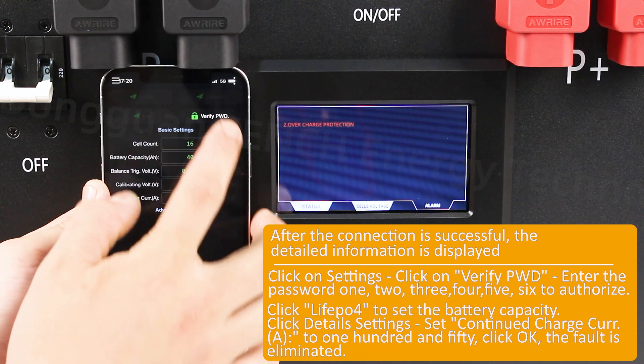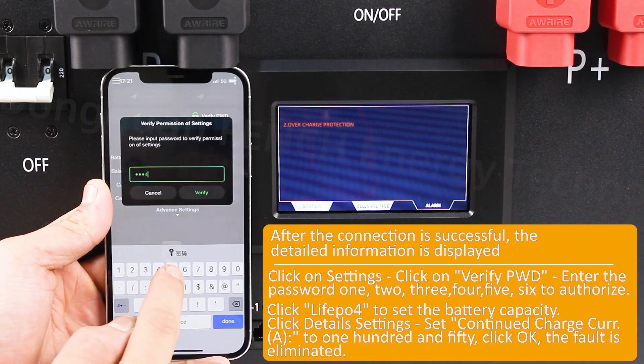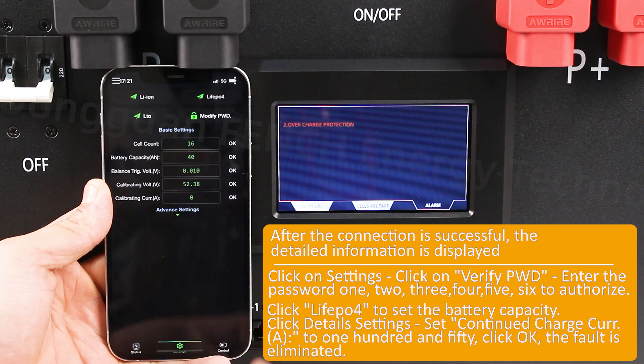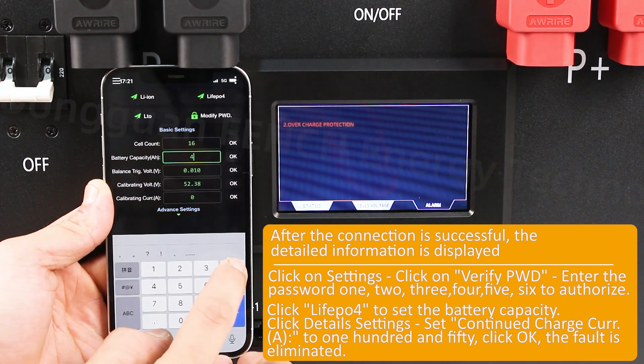Click on Settings, click on Verify, and enter the password 1, 2, 3, 4, 5, 6 to authorize. Click "Lifepo4" to set the battery capacity. Click Details Settings, set continued charge current (A) to 150, click OK — the fault is eliminated.